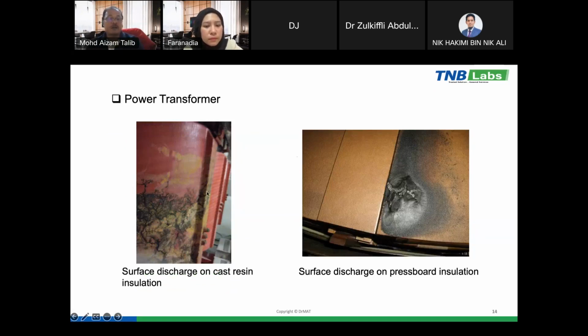And then for the power transformer, when the power transformer is operated at a higher temperature, in this picture we can see the presence of surface discharge. It is a kind of discharge that happens at the surface of the insulation on the cast resin transformer due to the overstress of the operation of the winding. It has caused the surface discharge. And then also we can see here in the second picture the surface discharge on the pressboard insulation. This is more on the oil-filled power transformer. So through this partial discharge measurement, we are able to detect the presence of these partial discharge activities.